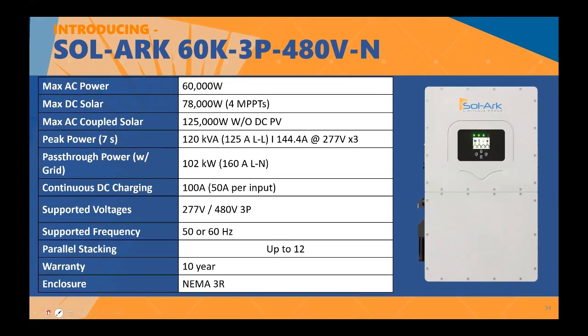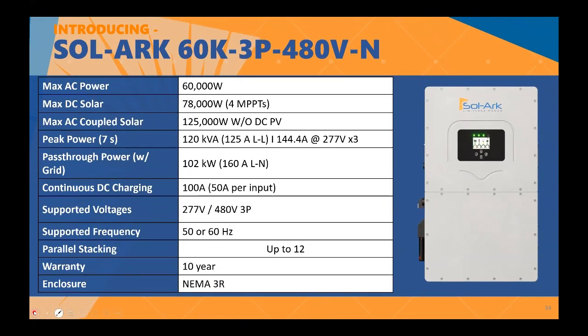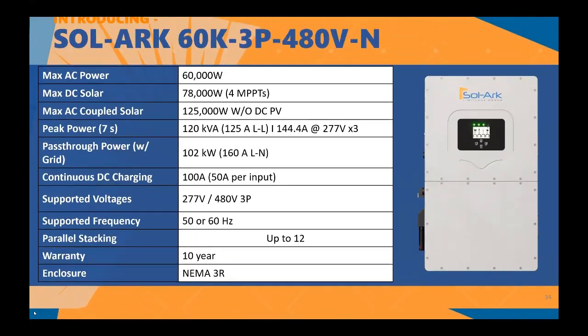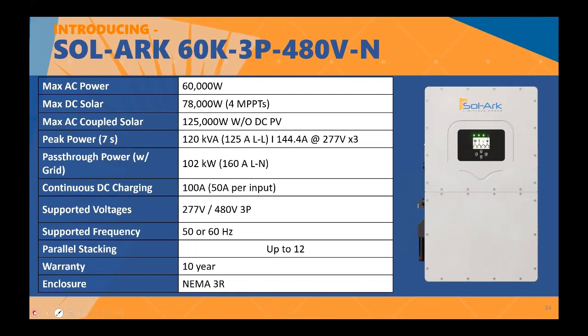For the 60K, we have similarities with the 30K. The main difference is that the maximum AC power you can connect into the 60K is, as the name implies, 60 kilowatts. And on this unit, you can connect 78 kilowatts coming from your PV array, distributed evenly into the 4 MPPTs, 19.5 kilowatts each. On this one, you can only do 277 and 480 voltage for 3-phase, and you can also stack up to 12 units.